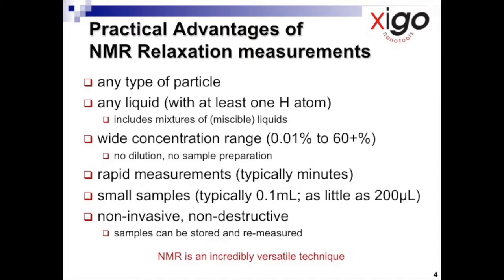Second, you can work with any liquid as long as it contains at least one hydrogen atom. For example, we can make measurements in hexane but not carbon tetrachloride. Even mixes of miscible liquids such as ethanol-toluene can be used. This is a very useful benefit, particularly when working in non-aqueous media and when investigating the wettability of surfaces.